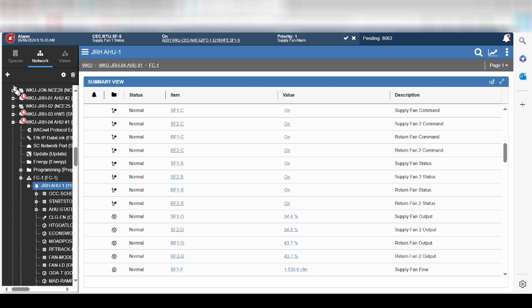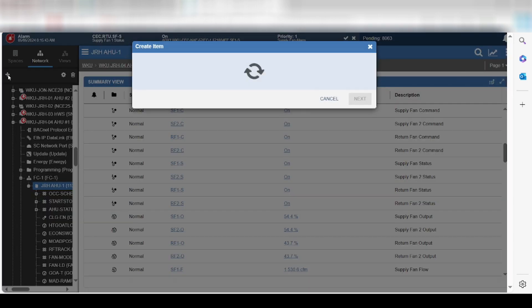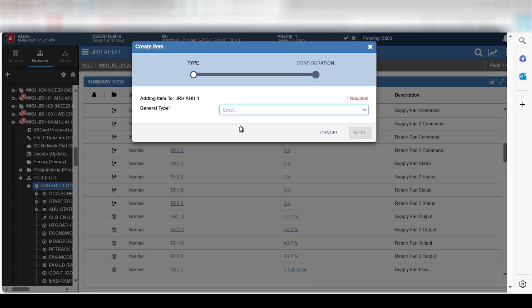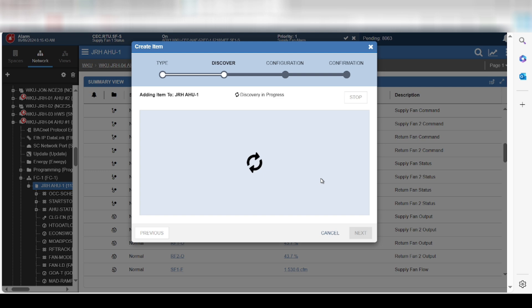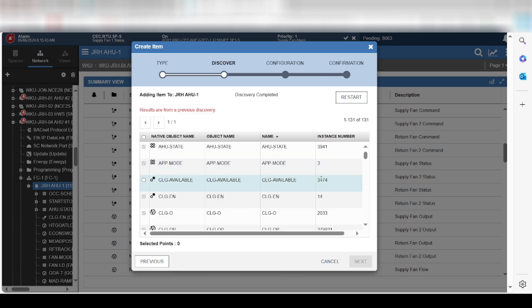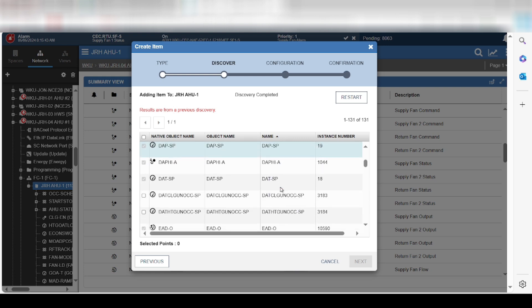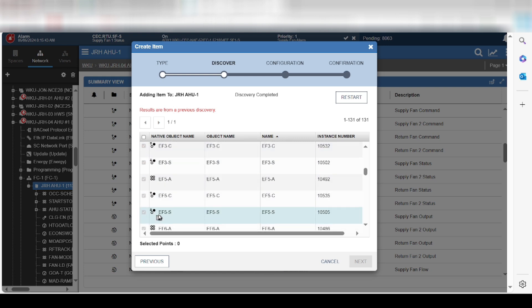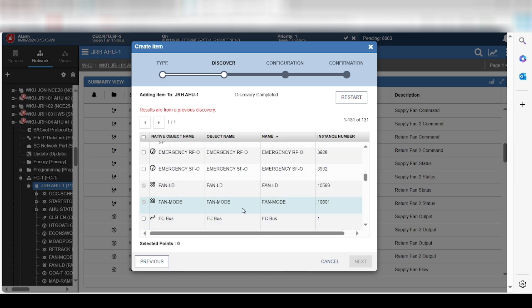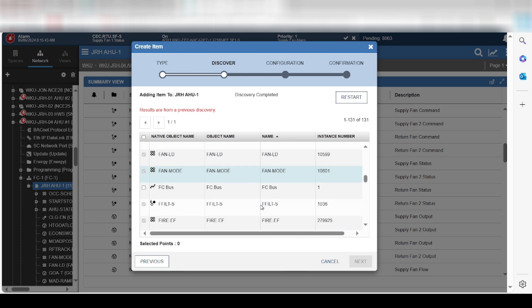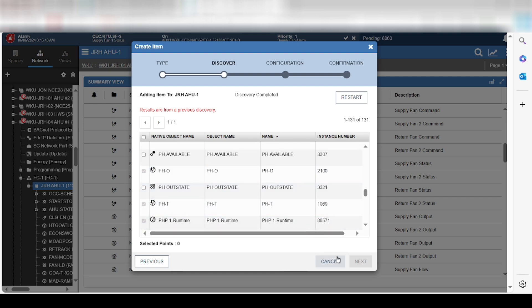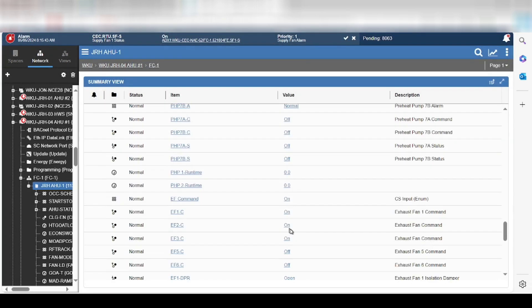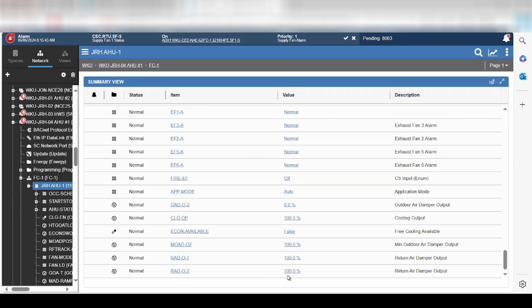The first thing you want to do is go to the device on the network tree, hit the plus sign, and then discover those new control points. This is after you have downloaded the new programming into your device. You simply select the plus sign and it's going to walk you through the process — drill down into all of the points in that controller, find the points you want, and add them to the network tree of your system.